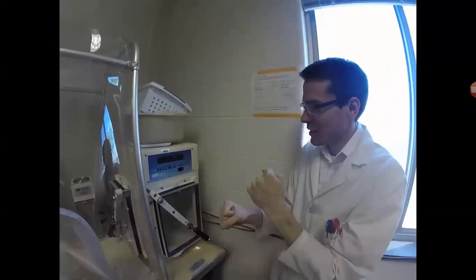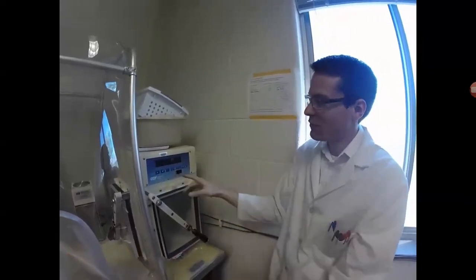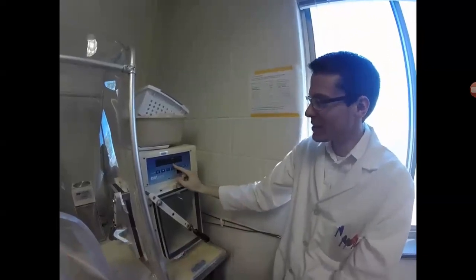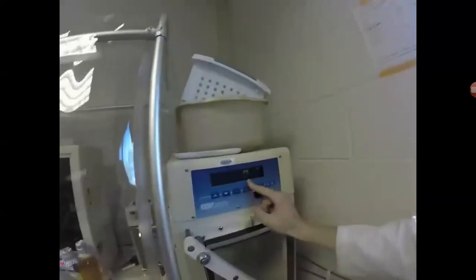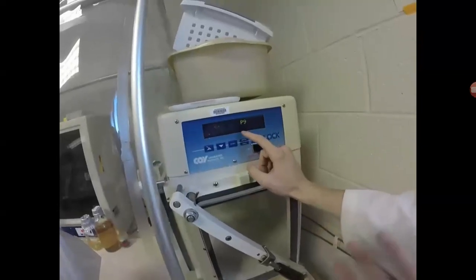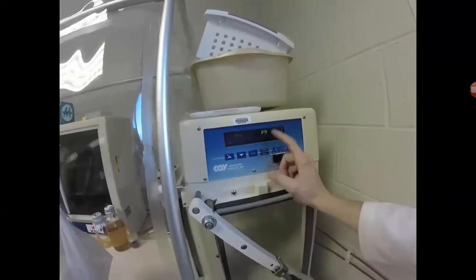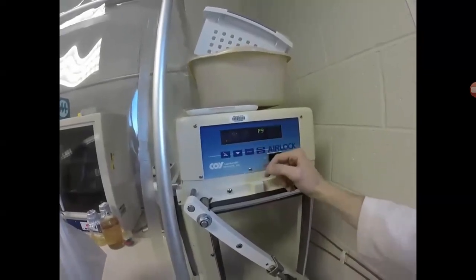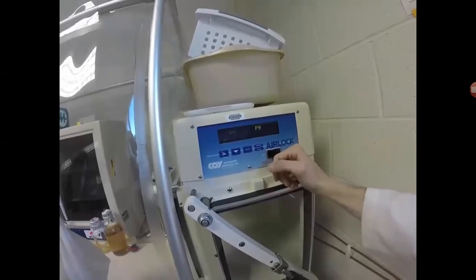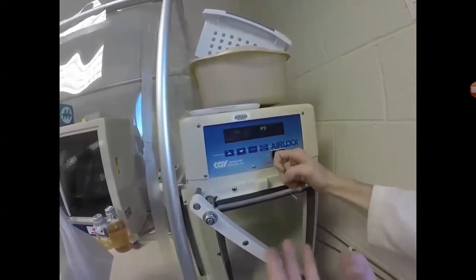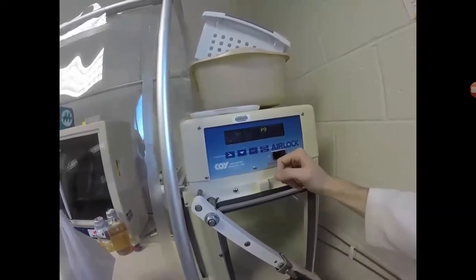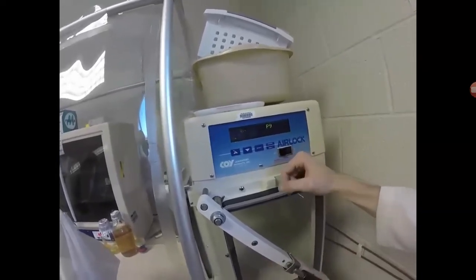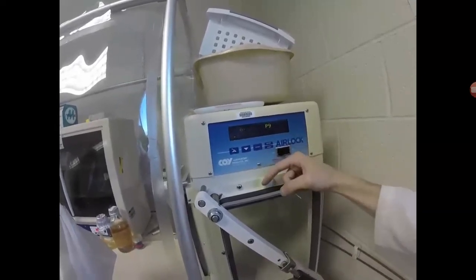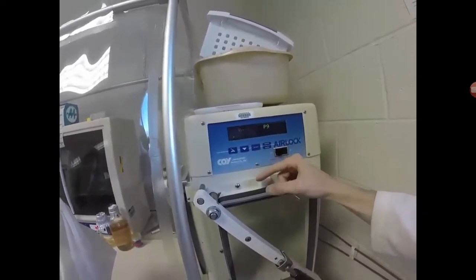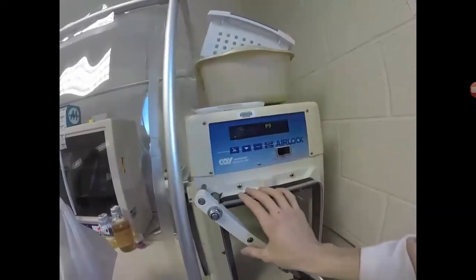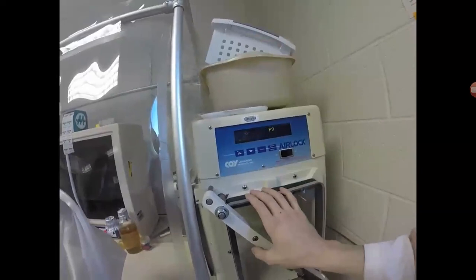And other than that, the only other thing to mention is that right now it's sort of confusing time because, as you can see, we've come back to the P9 screen. Do you see the screen? There you go. And we know that it's anaerobic because we were just working with it, but at this point, it doesn't actually tell us that. So if somebody new were to come in, they would have really no idea whether it's anaerobic or not. So my philosophy is just always assume that it's aerobic. And if you want to open the inside door, you need to run the cycle, unless you know for sure that it is. For example, we know now that for sure it is anaerobic. But if somebody new were to come in, they should assume that it's always aerobic so that you don't pump the chamber full of oxygen, because that could be bad.